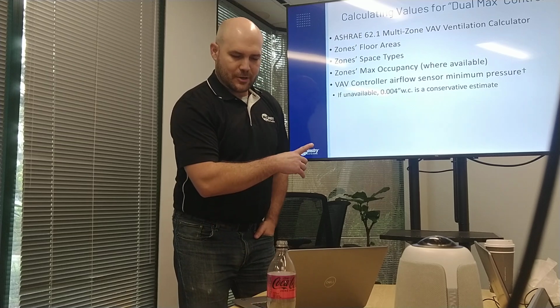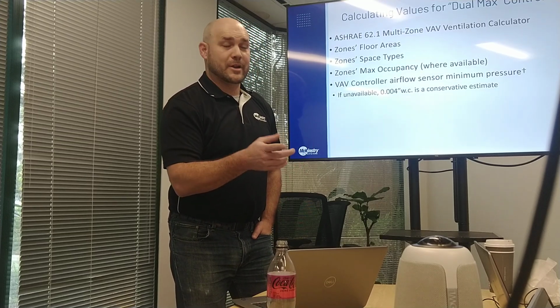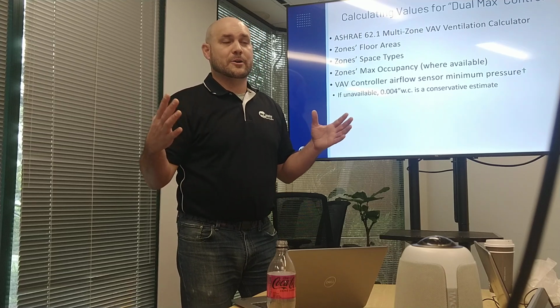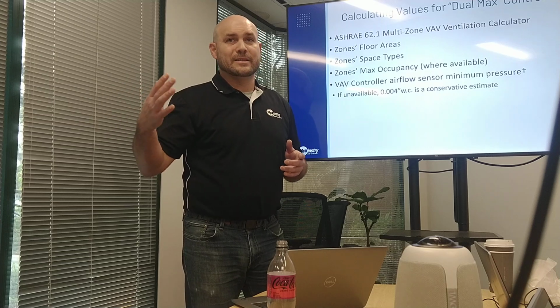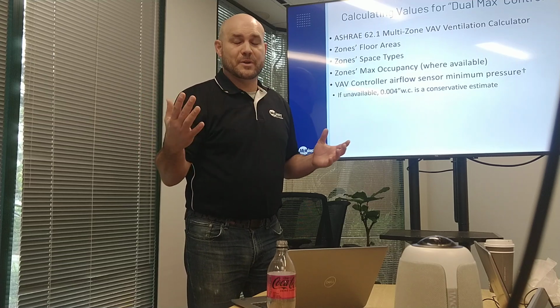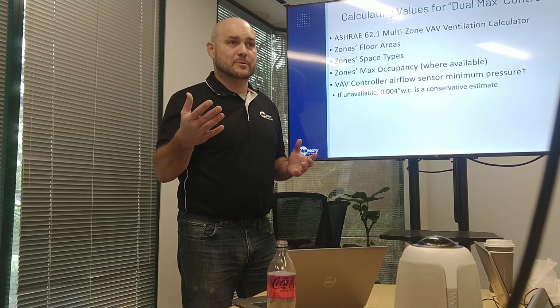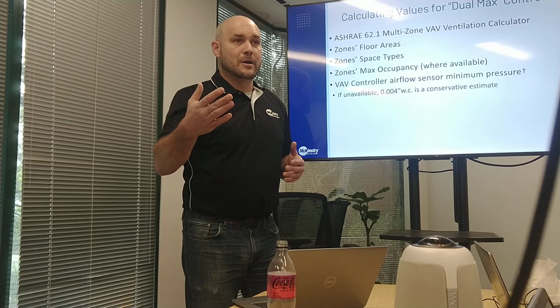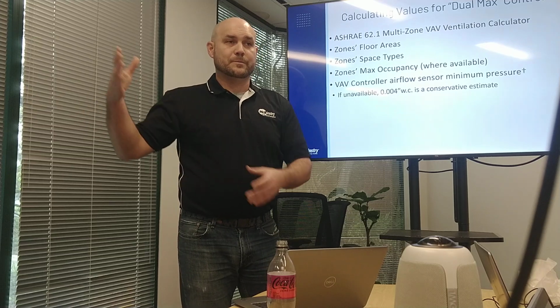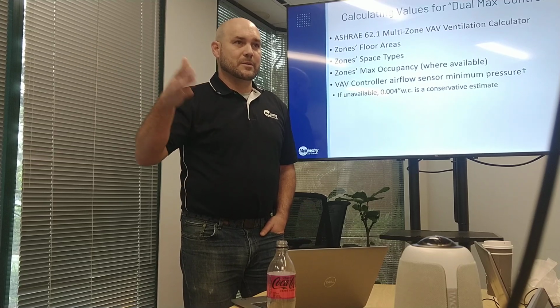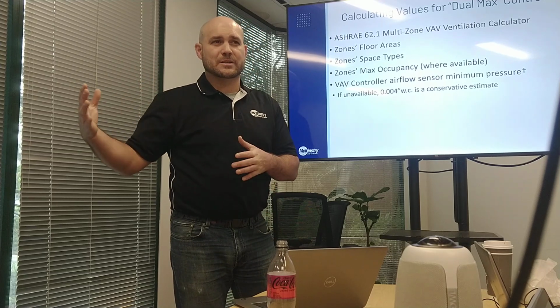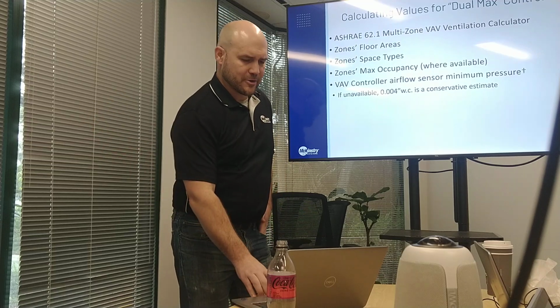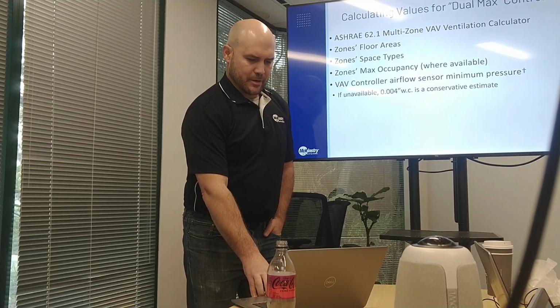I have a chart on an upcoming slide, but I haven't actually done that calculation, because you might use a box that has a maximum of 500 CFM, but depending on zone size and zone load, it might only have a maximum cooling load of 200 CFM. And in another instance in the same building, it may have a maximum cooling airflow of 450 CFM. So to say that it's always going to be 15% or 20% of that isn't really good. It would be a function of the max box flow, which is getting into manufacturer data rather than zone demand. Got it. Okay.